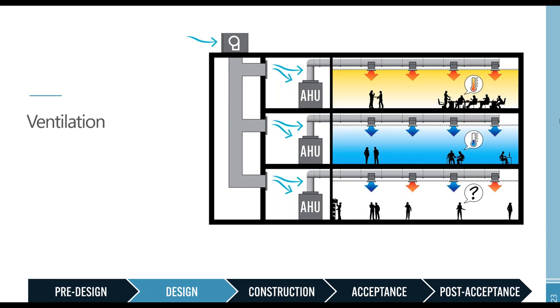This raw outside air was dumping into an occupied building with seemingly no steps being taken to ensure that that volume of air could be properly treated by the air handling system. Basically, they were going to overwhelm the system, was my concern, and they weren't going to be able to meet all the required set points. So I brought this issue up.